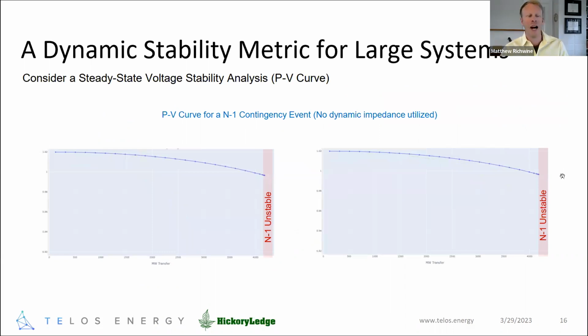Now we're returning to that steady state space I spoke of in the beginning, looking at this in a PV analysis lens. Very briefly, the plots I'm going to show have power on the x-axis — megawatts transferred from the sending end resource — and voltage in per unit on the other axis. As we increase the power transfer level, you see a decline in voltages on the transmission system, which, wrapped all the way around, generates our familiar nose curve.